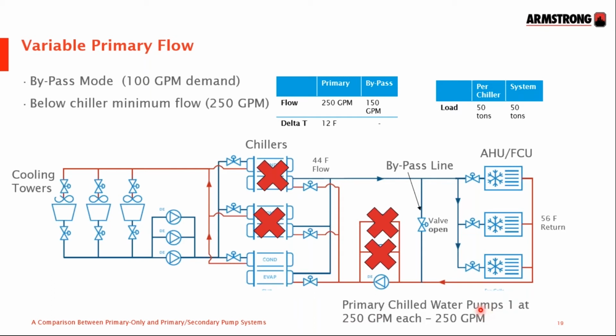During this operation, the newly created loop around the chillers and pumps becomes constant flow, and the new loop here between the bypass and the load is a variable flow, which sounds like the constant flow, variable flow system we were looking at originally. But this only applies in bypass mode. Once the cooling load increases and the valves open up, the controls will close the bypass and allow extra flow through the system, and it's back to normal again as a variable primary flow.